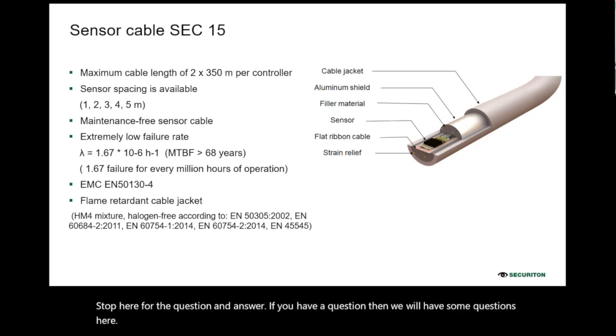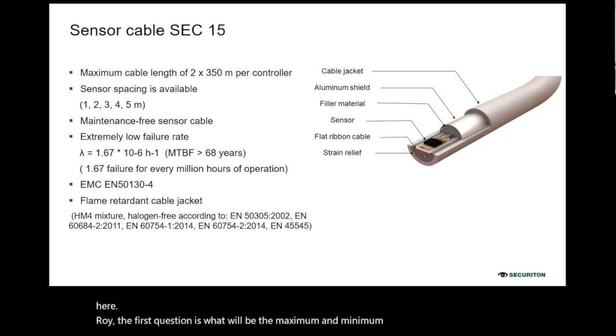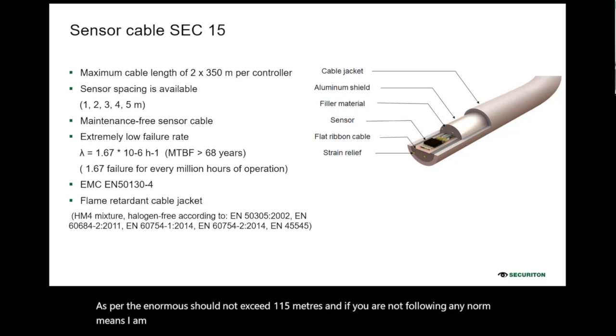So Rohit, the first question is, what will be the maximum and minimum length of one sensor cable? Of one sensor cable, or sensor tube. Okay. If we talk about the length, the minimum is 10 meters, and the maximum as per the EN norms should not exceed 115 meters. If you are not following any norm, then you can go up to 200 meters. So 115 meters as per the norm for one channel, and 200 meters for one channel without any norm.